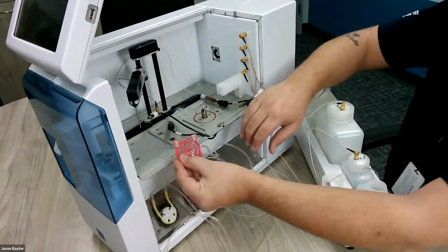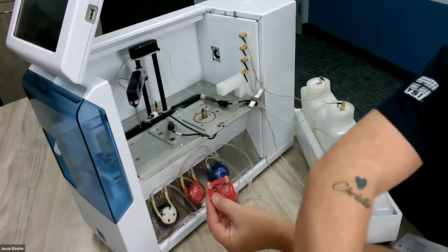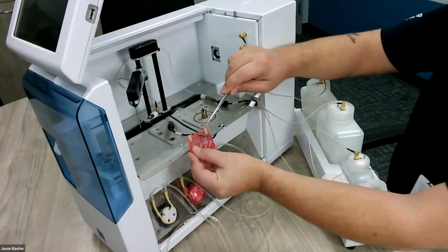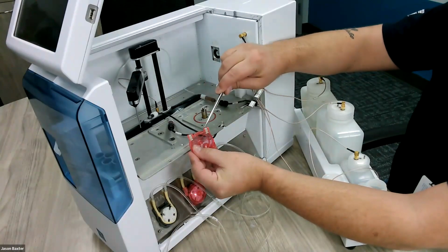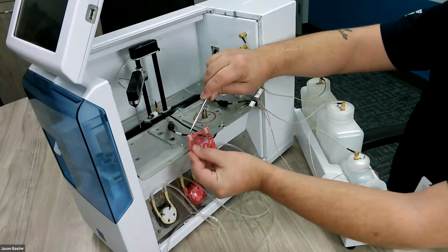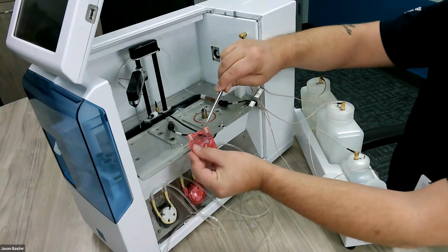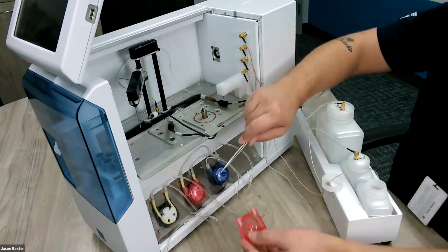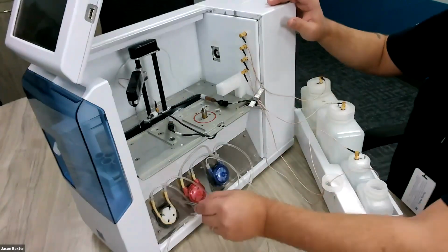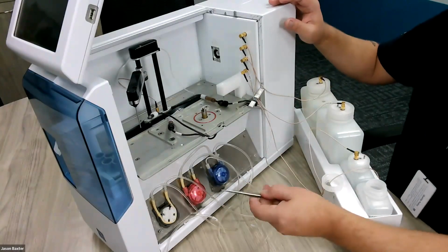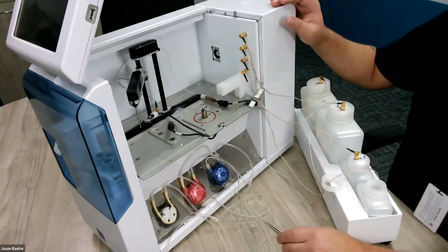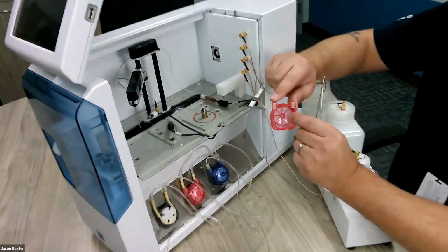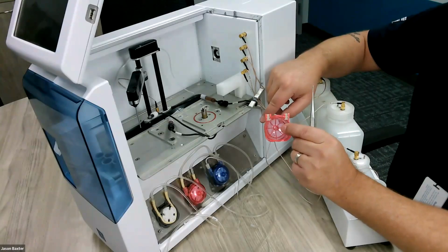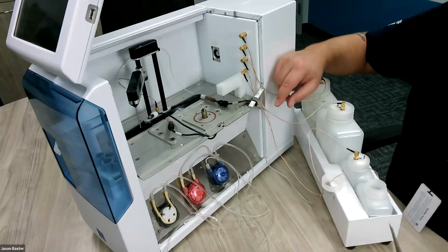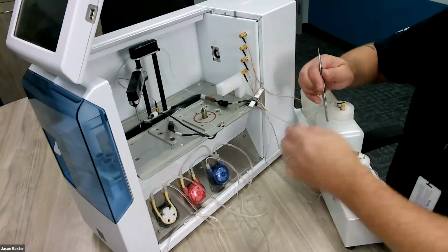For the calibrator, once you remove the calibrator pump, you should notice it has these 2 white rubberized inserts inside of this cap. Sometimes these inserts like to get somewhat adhesive and they will actually stick to the tubing here. If they do stick to the tubing, that's not a problem. Just remove them from the tubing and press them back into the cap. They just nest in. There's no glue. There's no snapping. They just sit in place. But it's very important to have them.